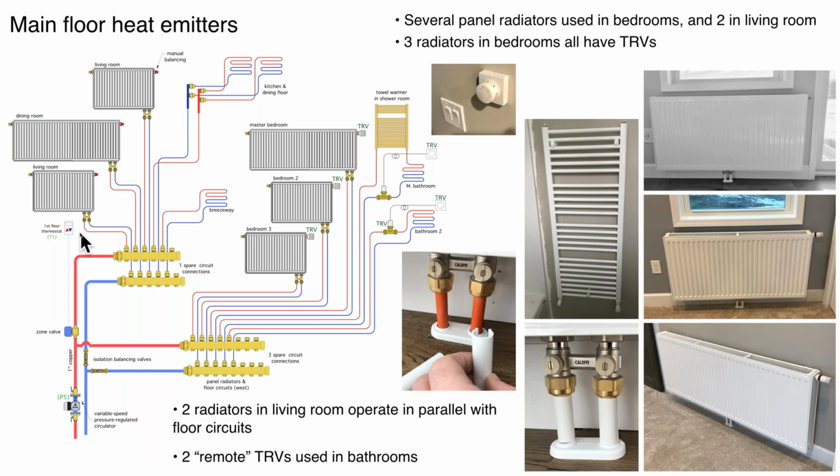You know, you could. It depends on how many. If you've got a lot of zones, I would always recommend a buffer tank anytime you have extensive zoning in a system. You could set up the boiler to maintain the buffer tank. That's a reasonable way to do it. You're going to get reasonable boiler cycles. Without a buffer tank, especially under part load conditions, it's really going to become a situation where we're trying to avoid short cycling the boiler, and a buffer tank goes a long ways towards eliminating those short cycles. So yeah, you could do the same thing with a boiler.